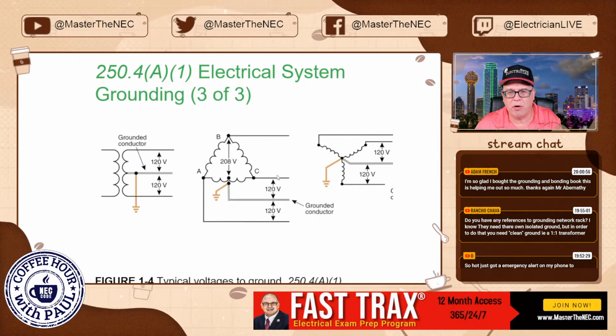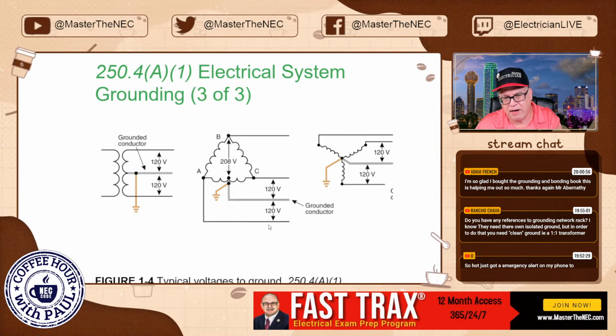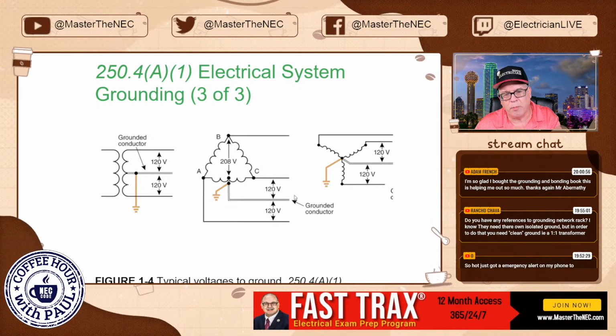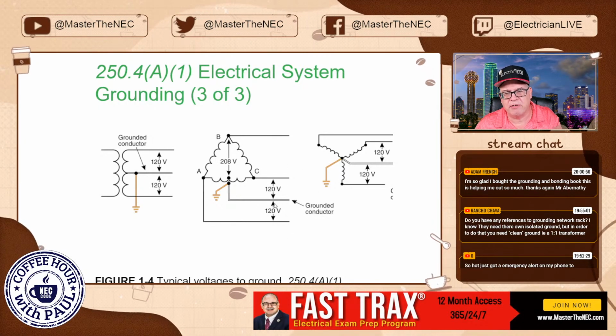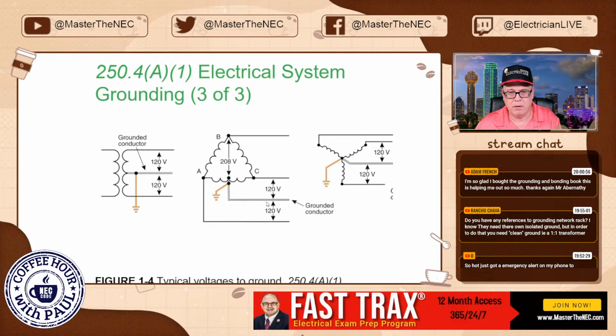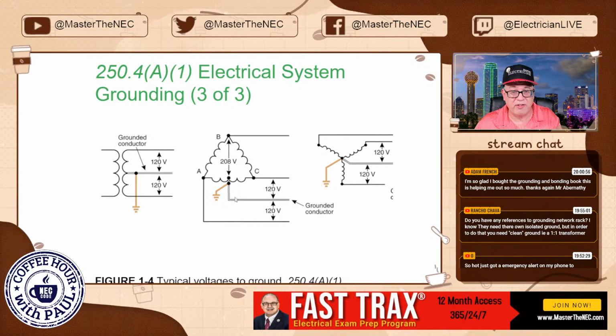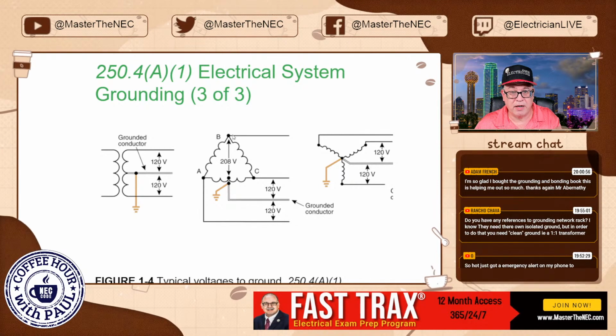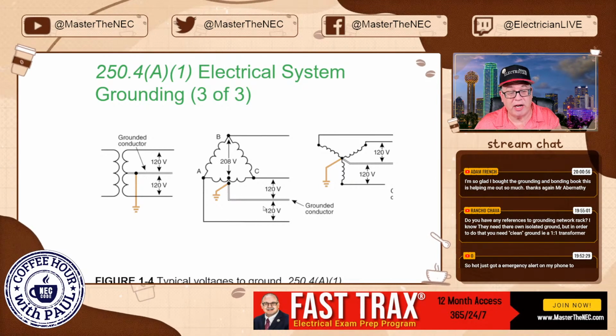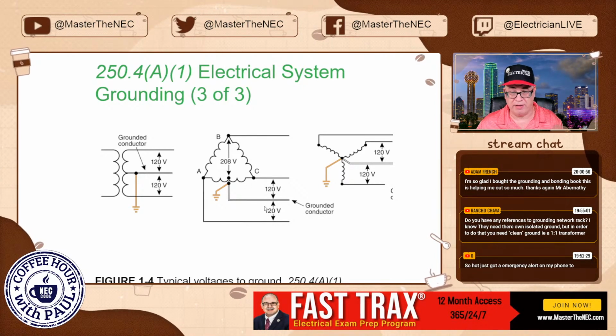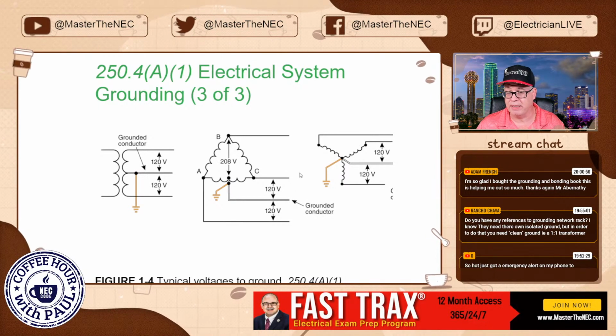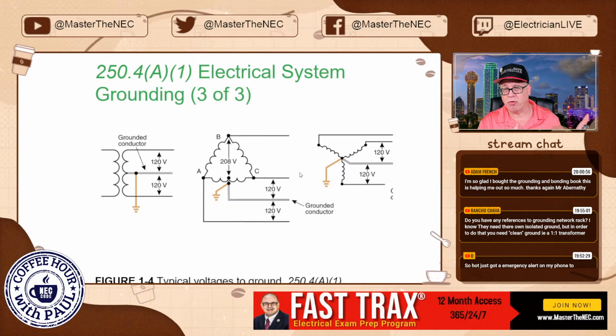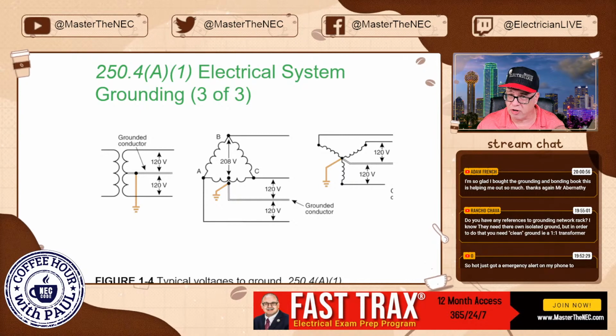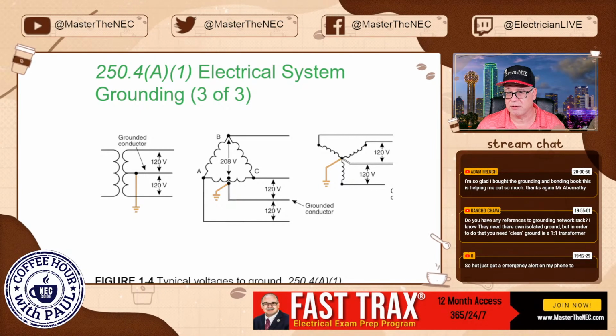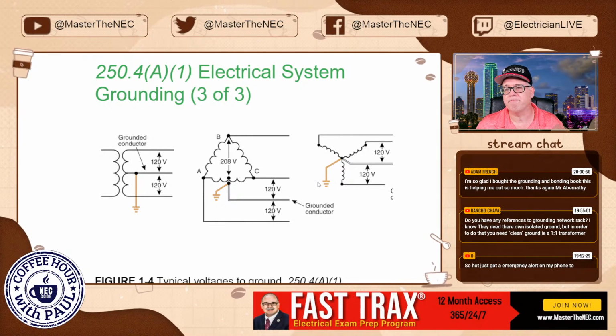Each one of these, depending on this leg of what's leaving to your premise, is going to be a grounded conductor, okay? Now, whether it's a neutral, this is not a neutral because of the B leg, but it is a grounded conductor because it's intentionally grounded. Okay, that's what I say. You might have a neutral, but if you make an intentional connection to earth, it's always going to be a grounded conductor. Might not always be a neutral, though.